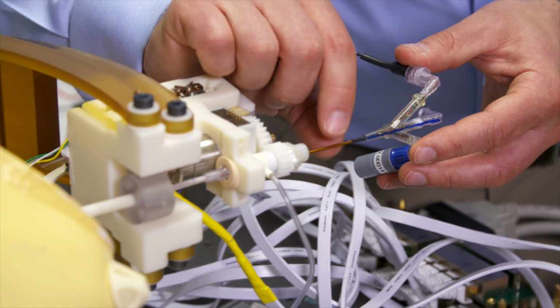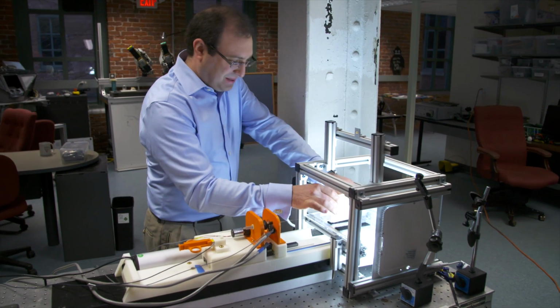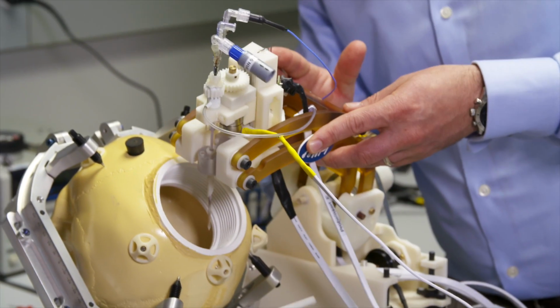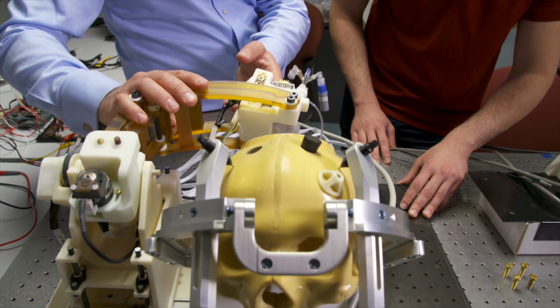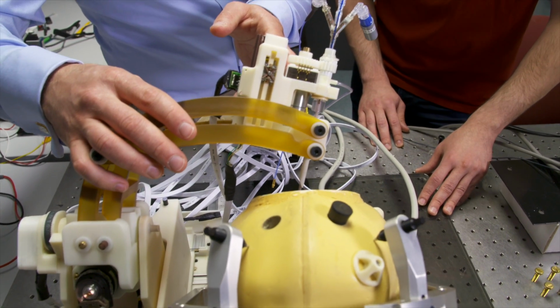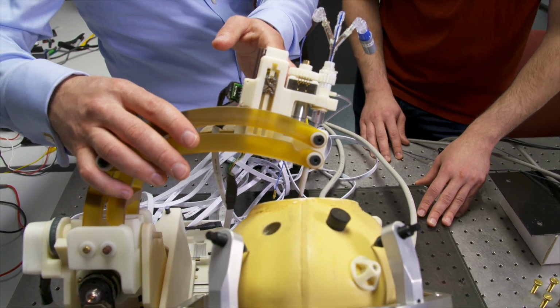Probably the hardest part is having it actuated inside the scanner and not affecting image quality. So most of the manipulator itself, the device that goes inside the scanner, is as much plastic as possible. We can use small amounts of safe metals such as aluminum and brass. In addition to the constraints of the materials on the robot, the spatial constraints of the bore make it very difficult to perform procedures inside of the MRI scanner.